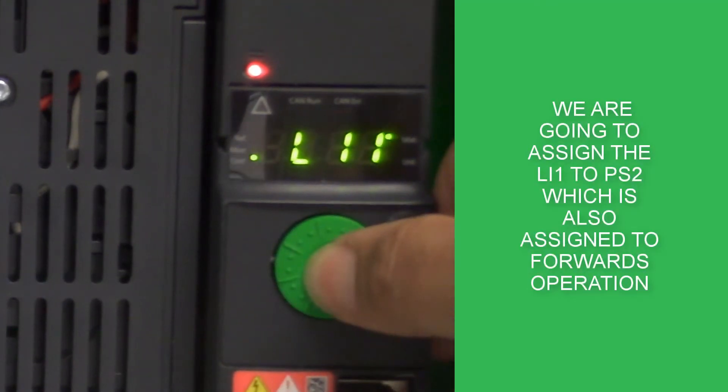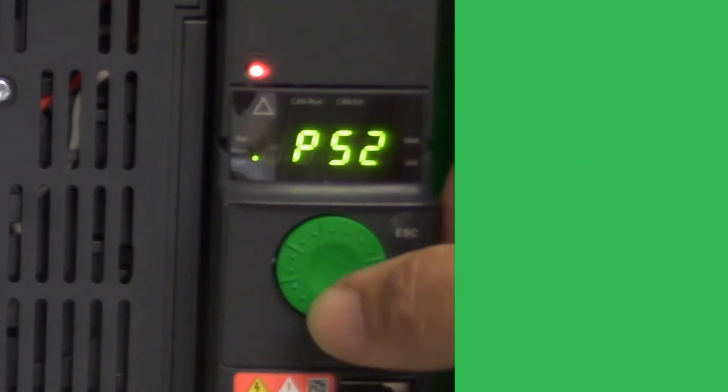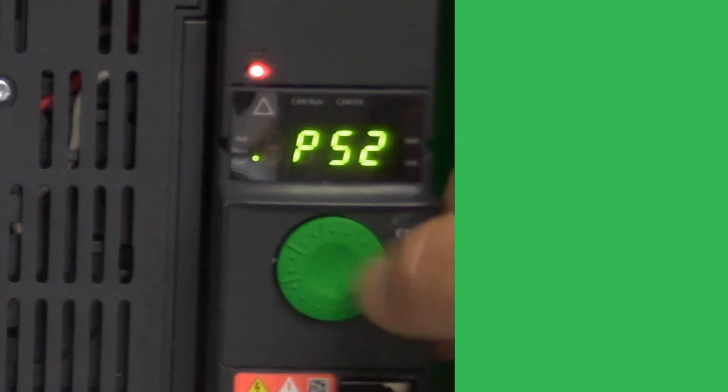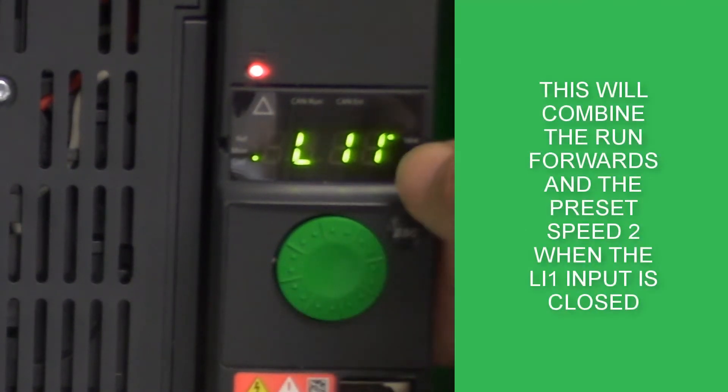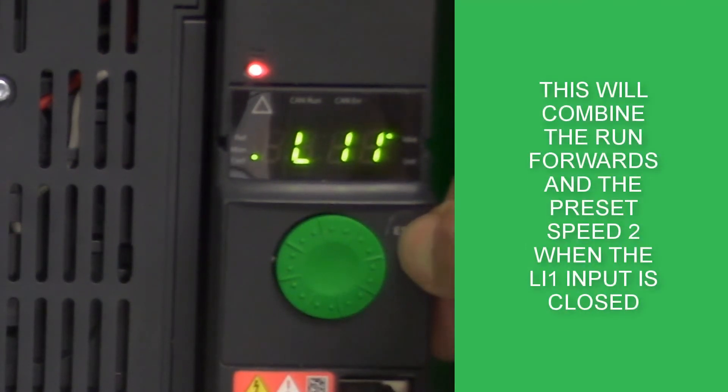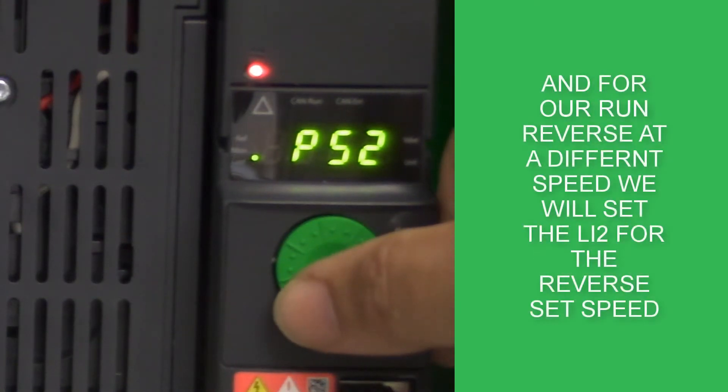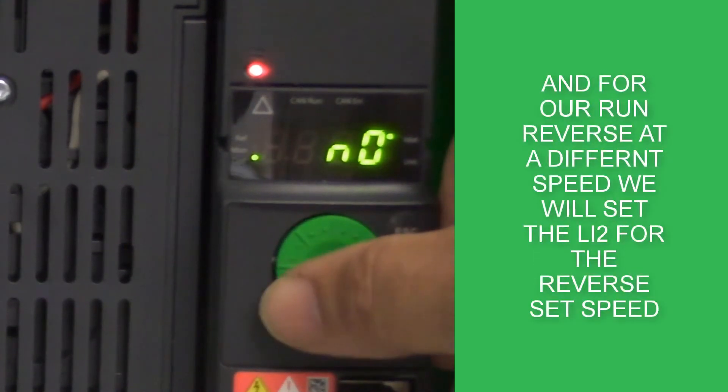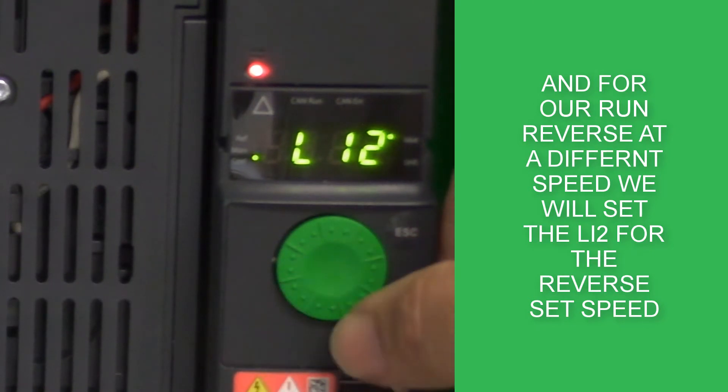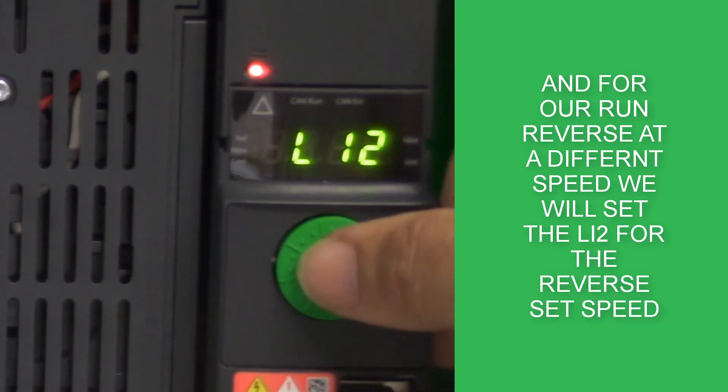First, I'm going to assign the preset speed 2 to logic input 1, the same as the forward input. Once I've assigned this, I can go to preset speed 4 and assign that to LI2, which again is assigned to reverse function.